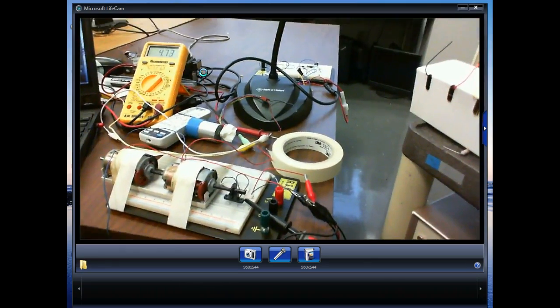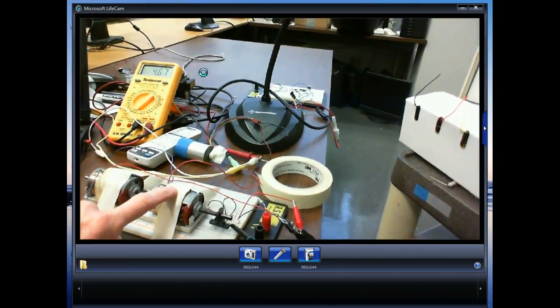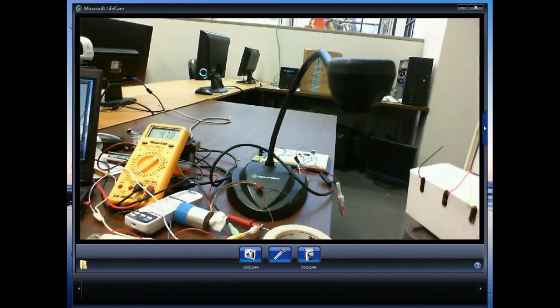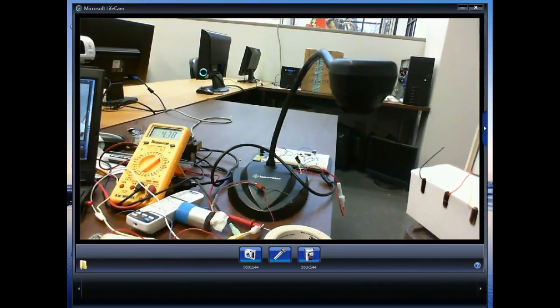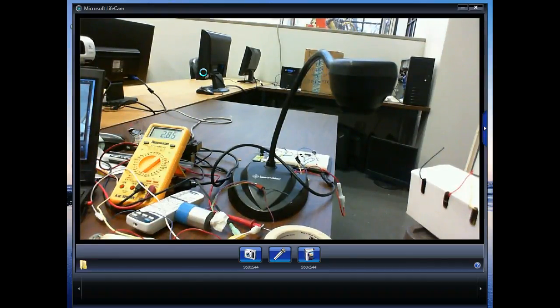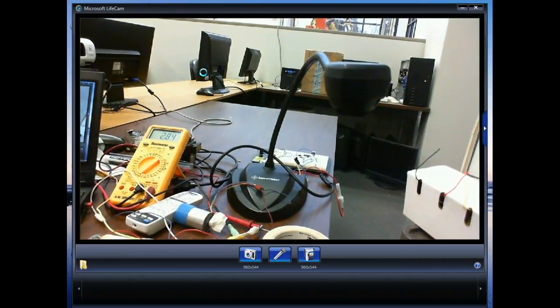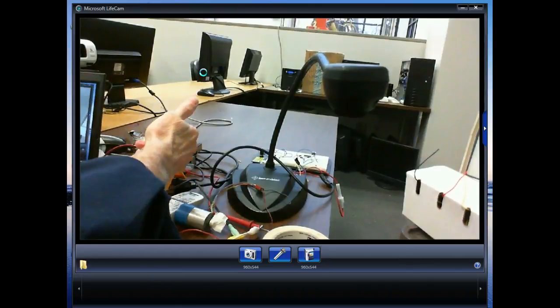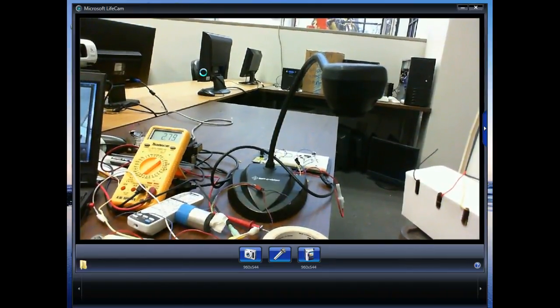Here's the setup right here. This is the motor, this is the tach generator. And of course, when I decrease the speed of the motor, voltage drops. So if I knew what speed 2.86 volts represented, then I could very easily tell, because it's linear, right? You understand? It means this guy varies exactly proportional to the speed. But then I have to know what that is, so you have to actually measure the speed of the motor to get that indication.